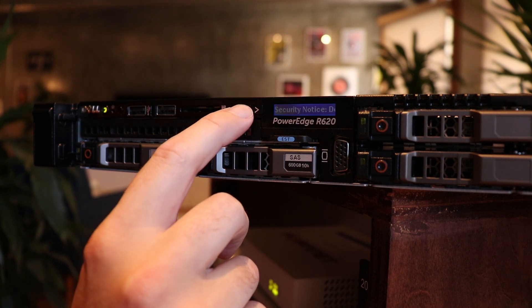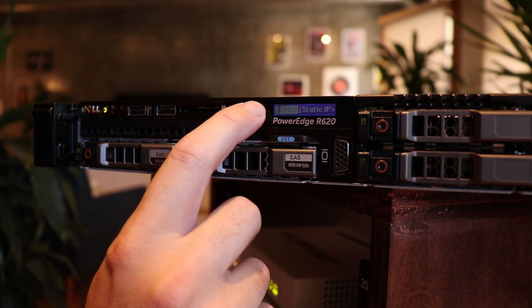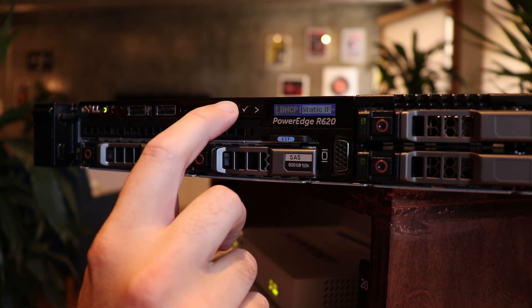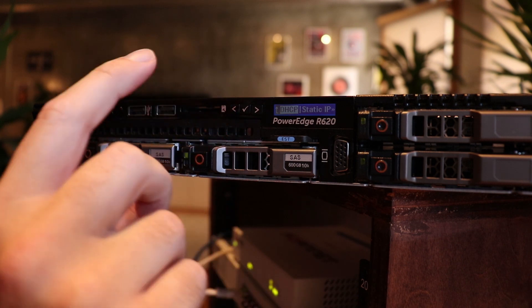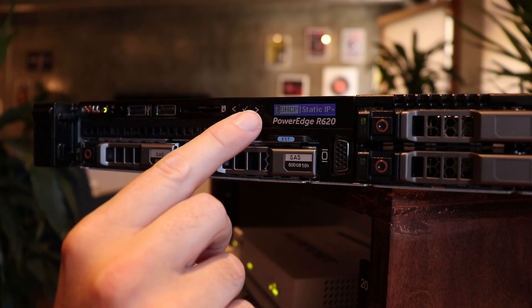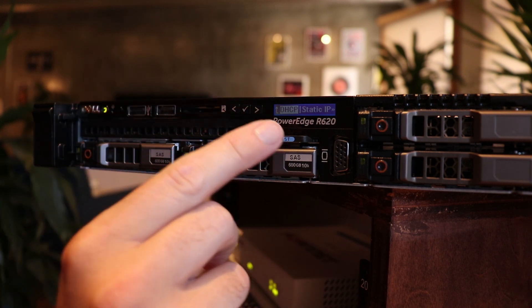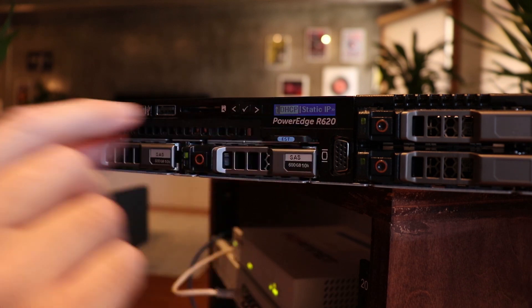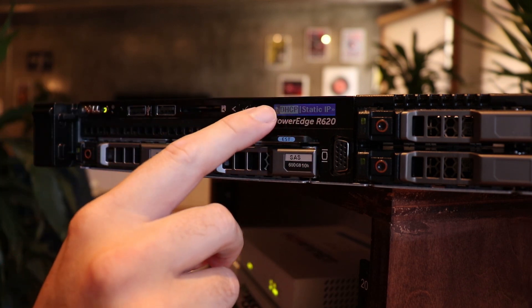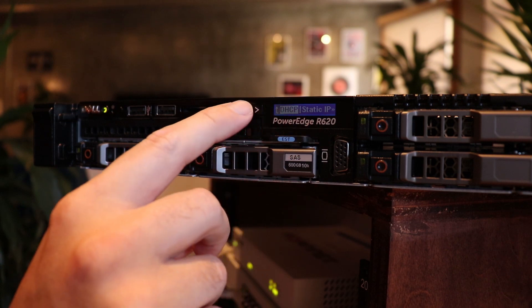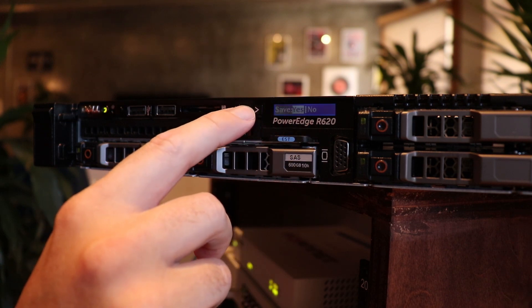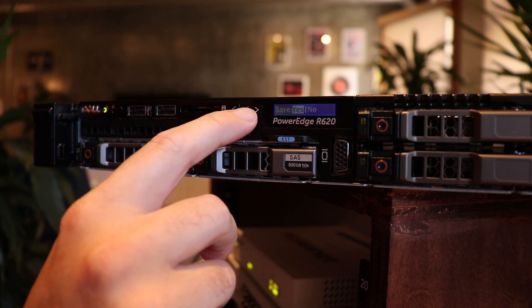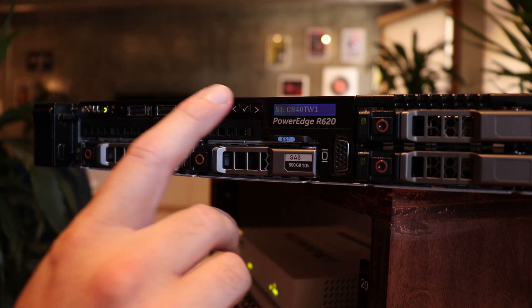Security notice. We don't care. All right. DHCP or static IP? Ultimately, I'm going to recommend that we make this a static IP. But for right now, we just want to get a DHCP IP so that we don't have to type it in using these tiny little buttons and this screen here. So let's do that. Let's hit the checkmark. Save. Yes.